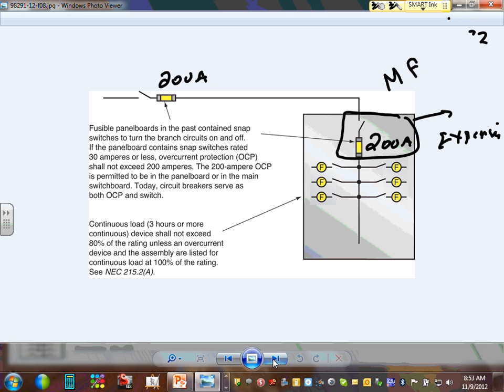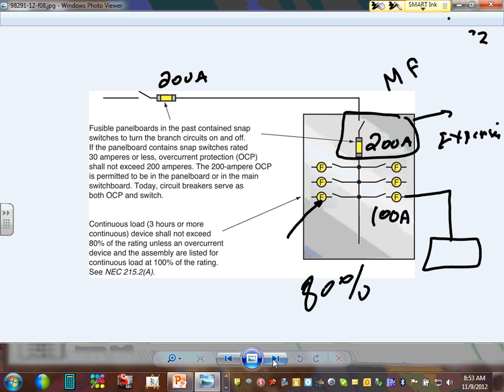When we size the fuses or circuit breaker, guys, remember that 80% continuous load. I cannot rate a fuse or a circuit breaker more than 80% of its size. For example, if this fuse was 100 amp, can somebody tell me what's the largest continuous load they can pull out of this? You got it.